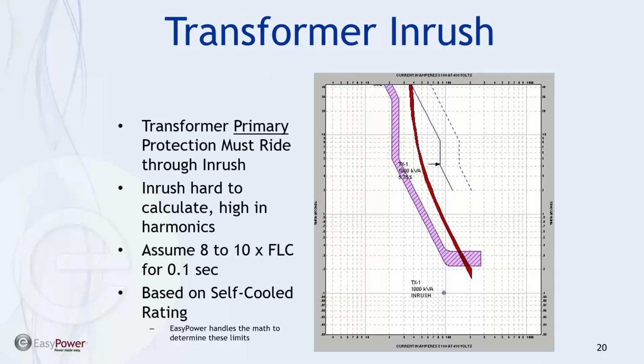So what we'll see is when we get into trying to size up protective devices for the transformers, we need to take into account the potential for exceeding the mechanical damage curve, the full 100% damage curve, and at the same time not have the protective devices sensitive or set so low that they are affected by the inrush when we first magnetize or energize the transformer. And so the transformer protection must ride through the inrush, which means it won't respond to an excursion that is represented by this little dot, and it's based upon some assumed variables or multipliers of the full load current. Usually it's 8 to 10 times the full load current for 1/10 of a second, and this is based upon the self-cooled rating.